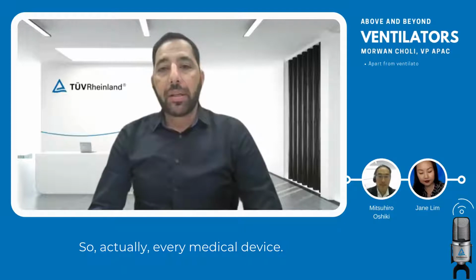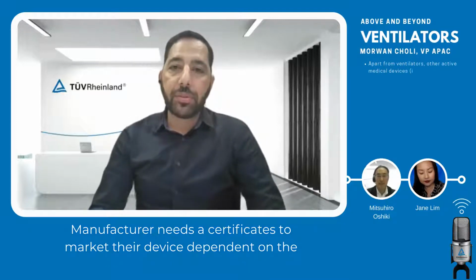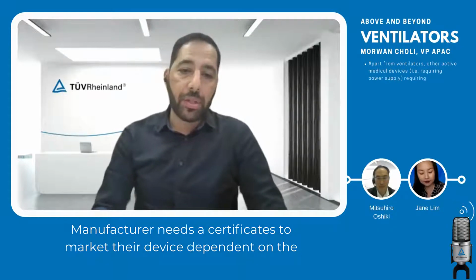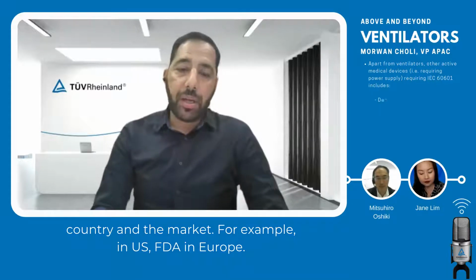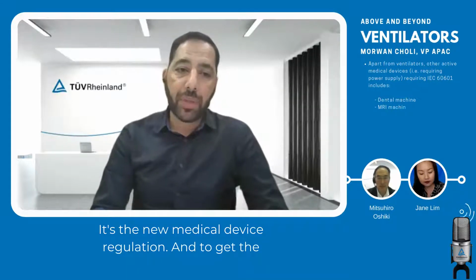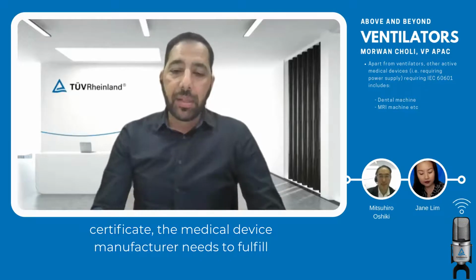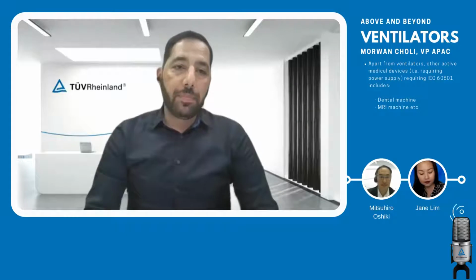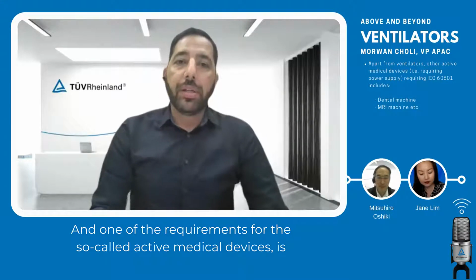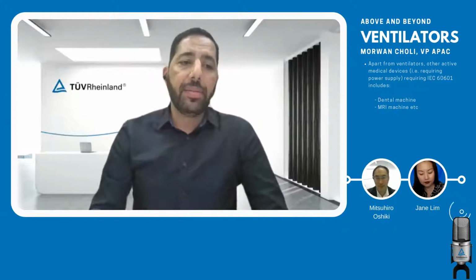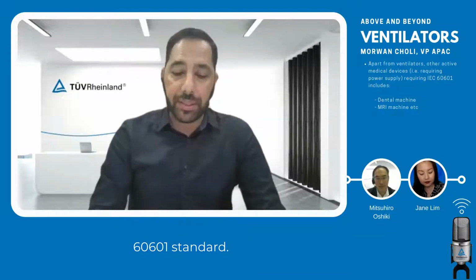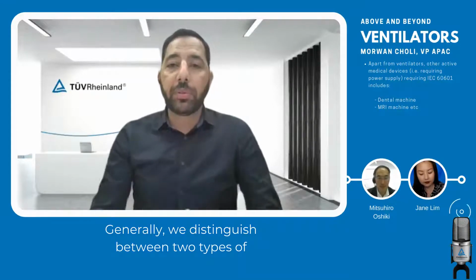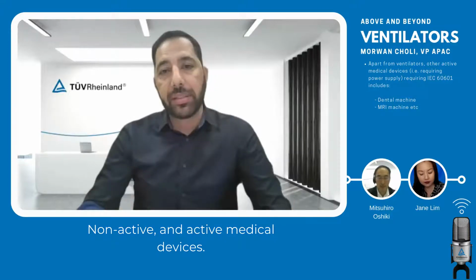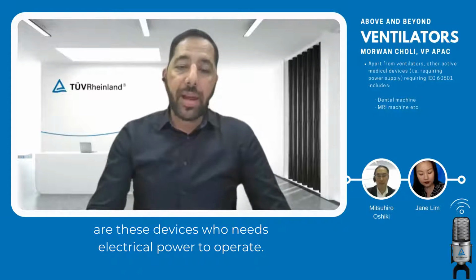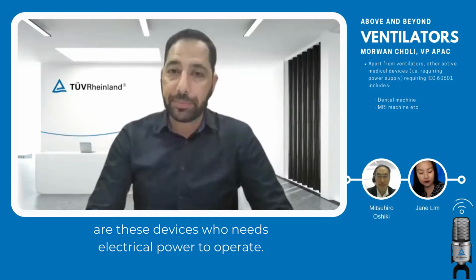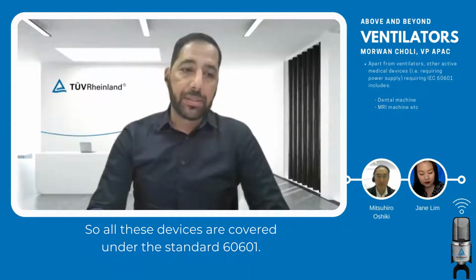So actually, every medical device manufacturer needs a certificate to market their device, dependent on the country and the market. For example, in the US, it's the FDA. In Europe, it's the new medical device regulation. And to get the certificate, the medical device manufacturer needs to fulfill different requirements. One of the requirements for the so-called active medical devices is the requirements of the 60601 standard. In general, we distinguish between two types of medical devices, non-active and active. The active medical devices are those devices which need electrical power to operate, and all these devices are covered under the standard 60601.